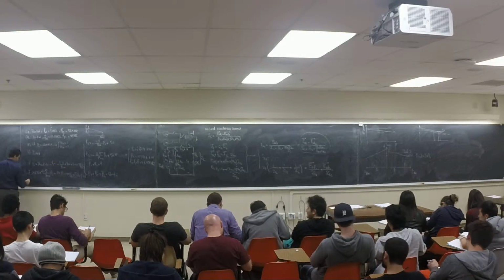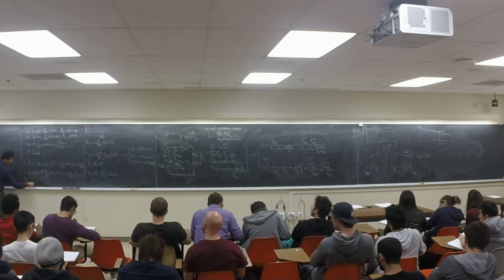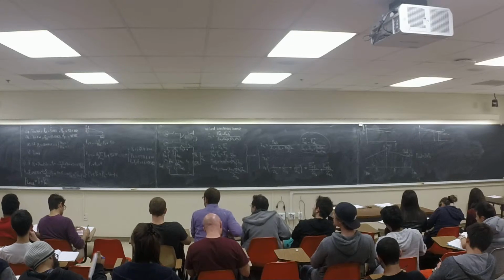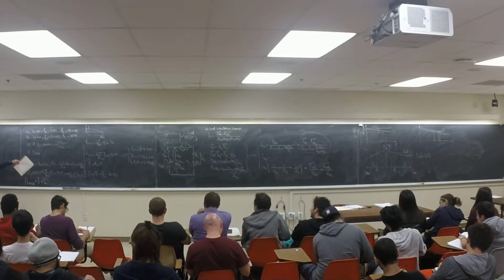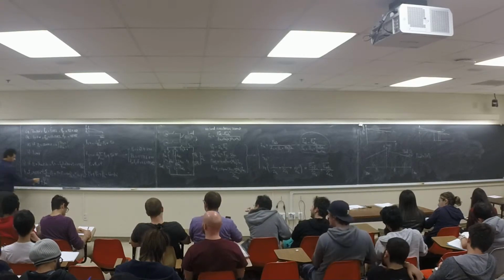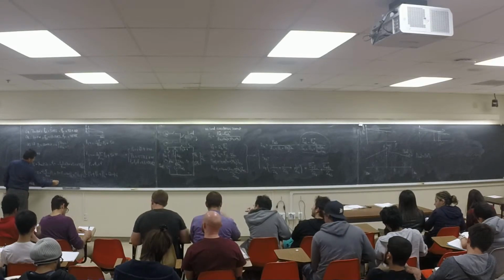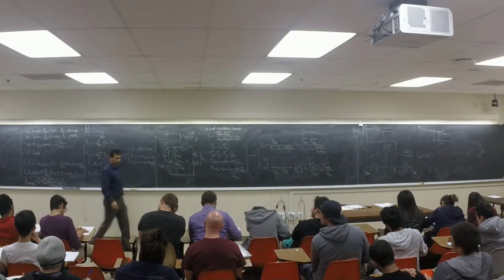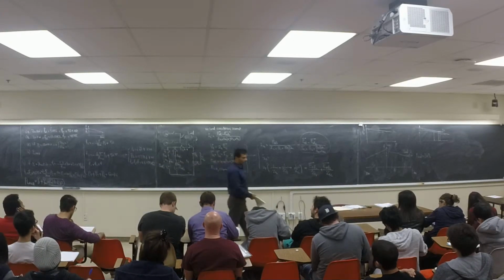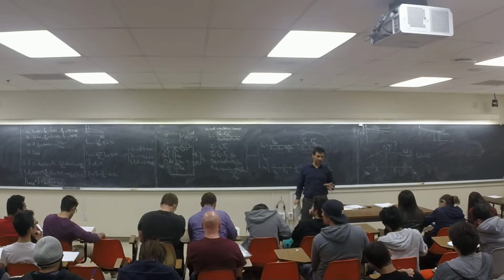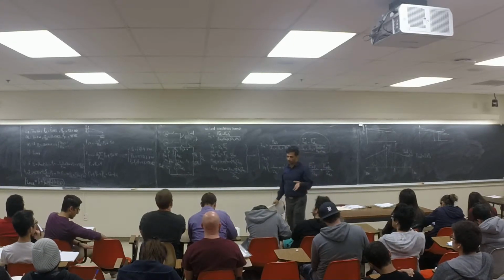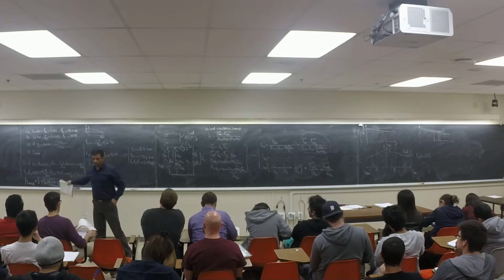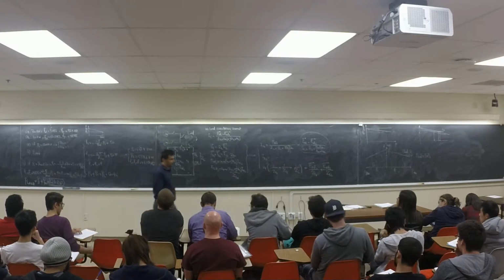So how much is the PL max we can support without overloading the generator? I'm not going to overload my generator, right? So 700 plus this one is how much? This is the maximum load I can support for this system. You can see this is the disadvantage of the generators: they are not exactly similar. Your system is 1400 kilowatt, but you can only support 1260 kilowatt. That's the problem.